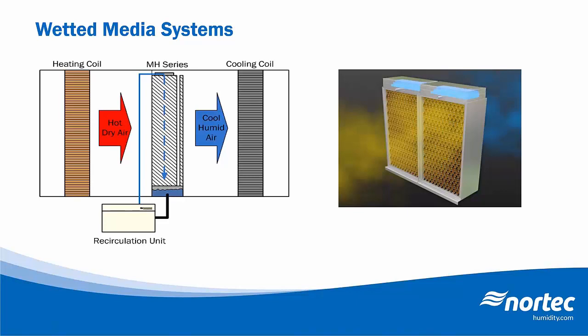So as water is evaporated from the system, minerals in the water will begin to concentrate and form a scale on the surface of the media itself. As a means to help control the mineral buildup, these systems will typically perform a blowdown cycle to drain some of that water out while bringing in fresh makeup water. So very, very little energy is required to operate this type of system, essentially just the power needed to pump the water over top of the media. There will be some additional fan power required to overcome the pressure drop, but it's still fairly low compared to traditional cooling systems.